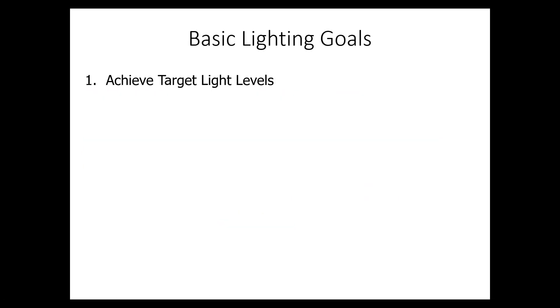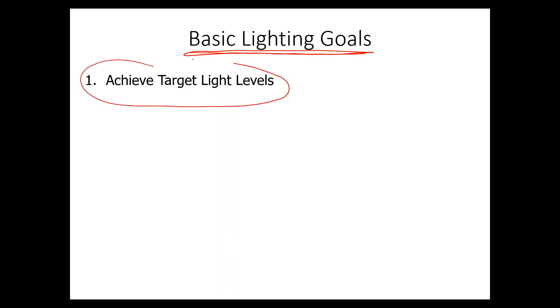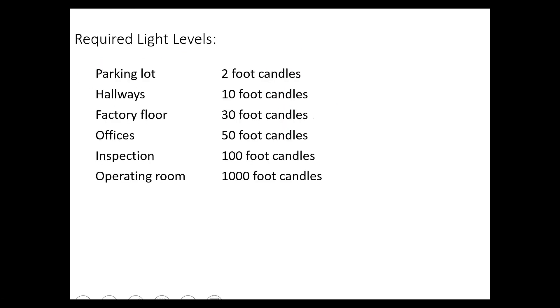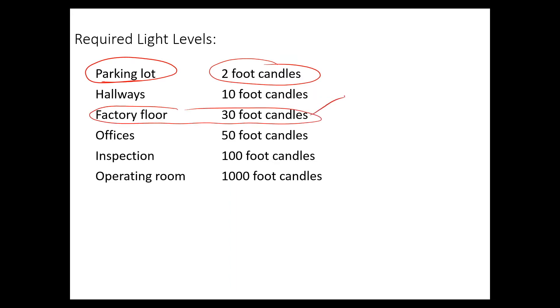Let's pull this information together and establish some basic lighting goals. In any lighting retrofit, you want to understand the target light levels, which come from an organization called the Illuminating Engineering Society (IES). They publish what's required in different environments. For example, in a parking lot you're only required to have about one to three foot candles. On a factory floor or aisleway, about 30 foot candles — and overseas this would be in lux; 30 foot candles equals about 300 lux. For offices or a writing environment, around 50 foot candles.